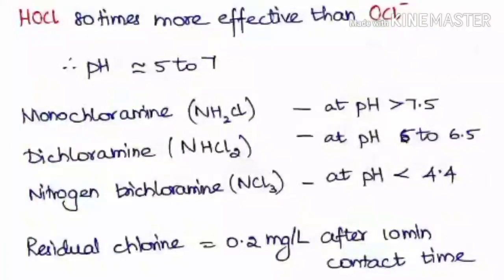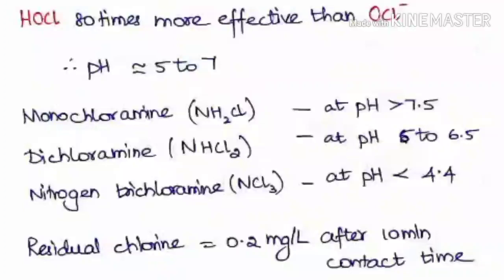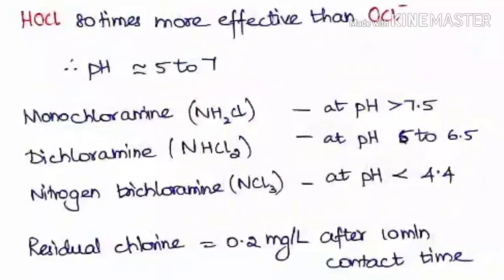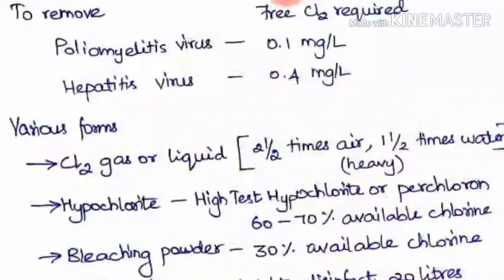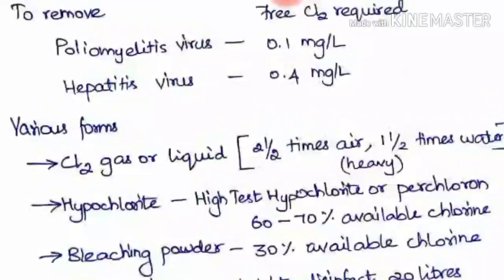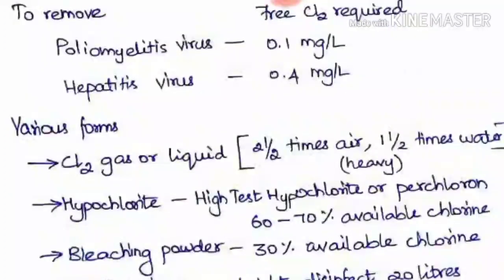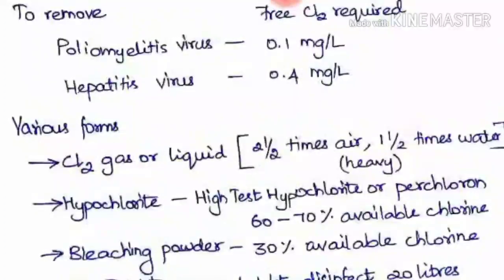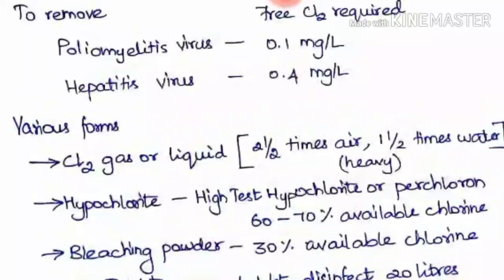Residual chlorine must be maintained in the water to take care of further contamination while passing through the distribution system. Nearly 0.2 mg/L after 10 minutes of contact time must be maintained. To remove specific viruses, for poliomyelitis virus the free chlorine required is 0.1 mg/L, and for hepatitis virus it is 0.4 mg/L.